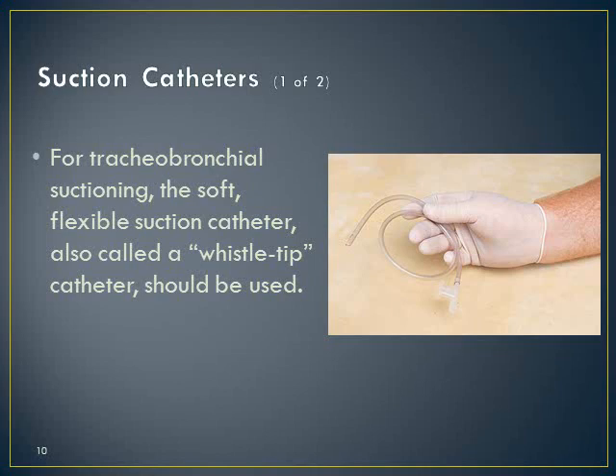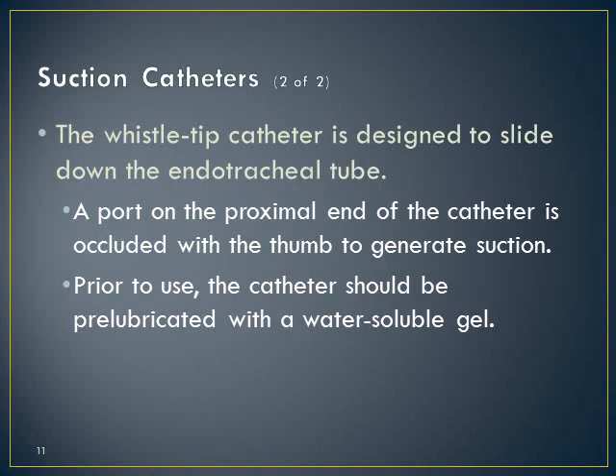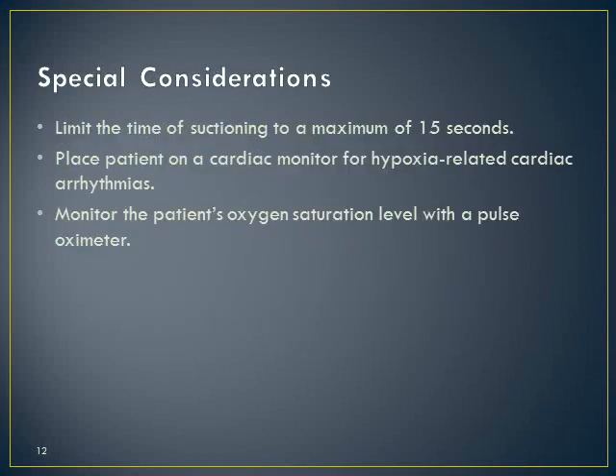The whistle tip is designed to slide down the ET tube pretty easily. It has holes on the side towards the distal end to minimize trauma to the tracheal and bronchial walls. And there's a port at the end that will allow you to occlude it with your thumb and activate that negative pressure as you withdraw the catheter. Again, you typically want to lubricate the tip with a water-based lubricant, or with water, or your saline solution, just to make sure that it slides down easier. So again, it is designed to slide in easily, and has all of the ports to activate the negative pressure, as well as numerous little ports at the end to help with suctioning out those secretions that are in the airway.